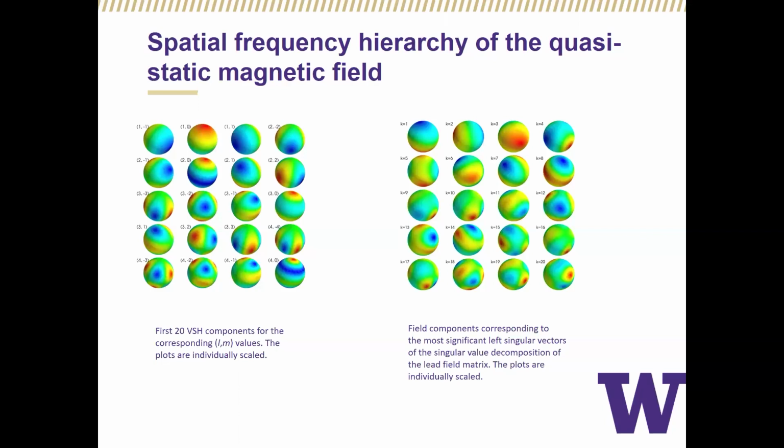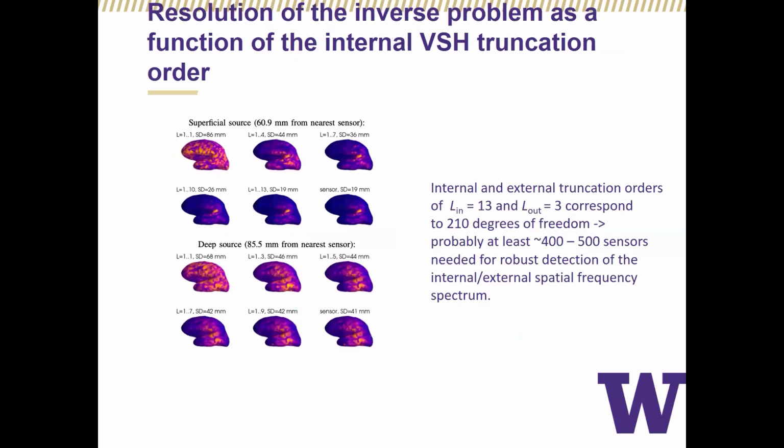And now the idea is that for high precision of the MEG measurement, we want to be able to detect as high spatial frequencies as possible. And obviously, if you can place a lot of sensors closer to the head, which is the case with OPMs, you can probably get higher spatial frequencies, and that way better spatial resolution.